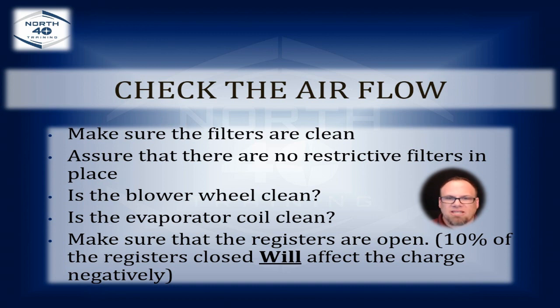The variable speed technology does help in that a little bit, but if you're restricting that airflow by closing the registers, you have unintended consequences of doing that with a variable speed blower, because once you start restricting that, the amp draw goes up and it starts to cost you some more money. And that's originally why you got that variable speed blower in the first place: one, to push the airflow, of course, but two, to save you money. No, it's only going to save you money if it's in the proper application, and restricting it is definitely not the proper application.